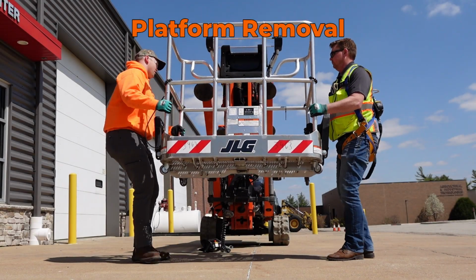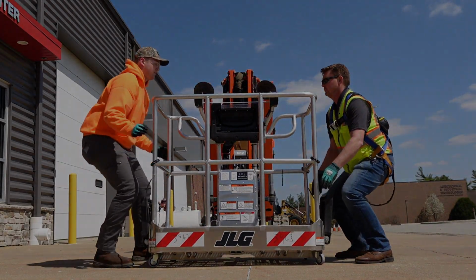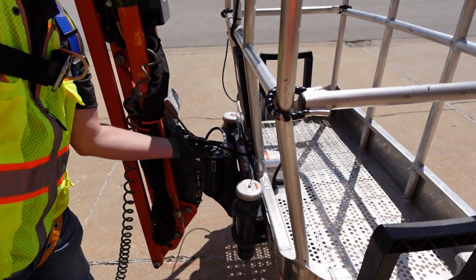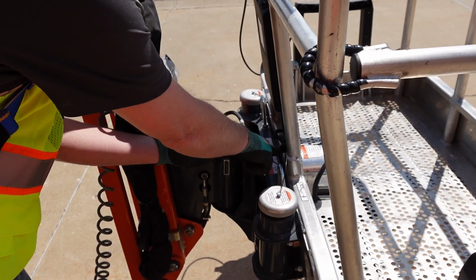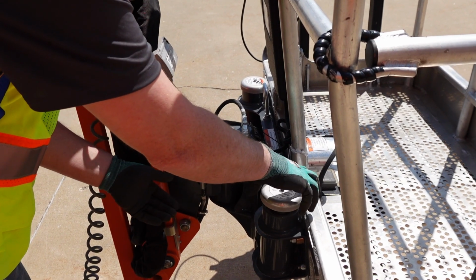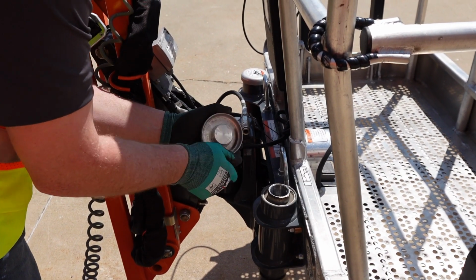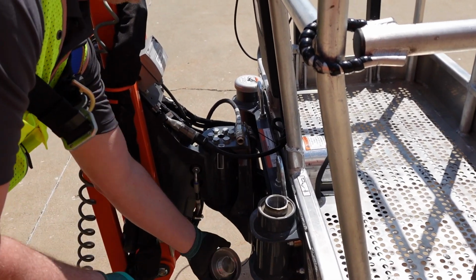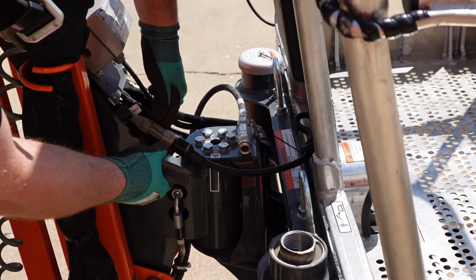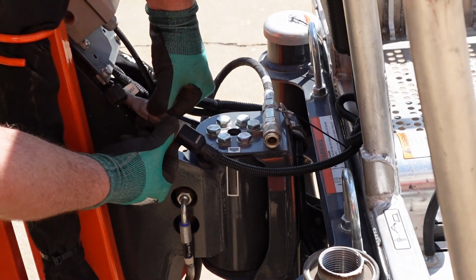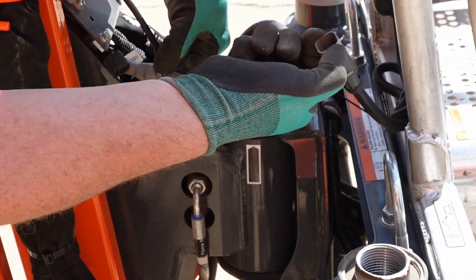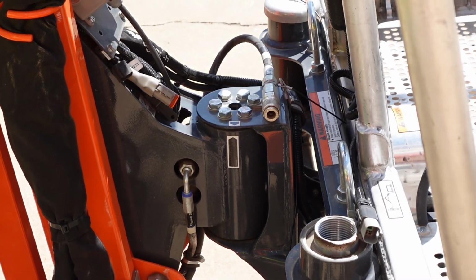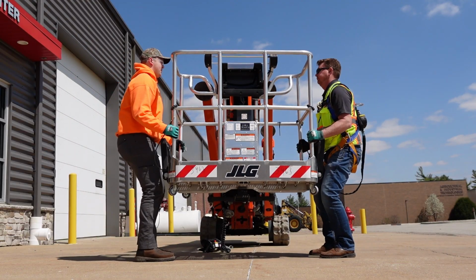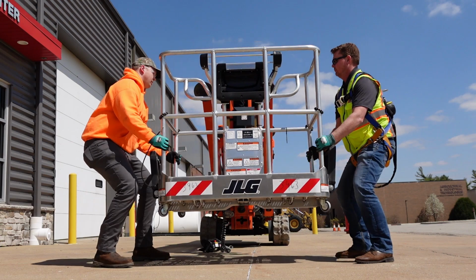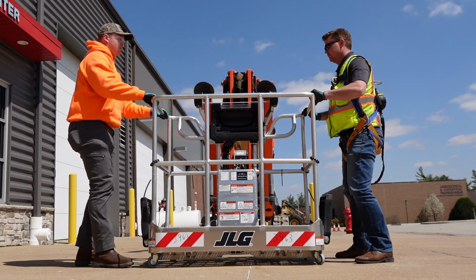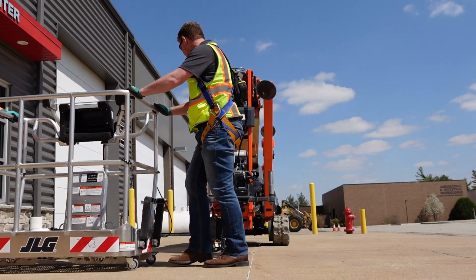The platform of the X660 can be removed for travel through narrow openings. A single wiring harness is connected to the platform. The platform is secured to the machine by 2 large, threaded caps. To remove the platform, unscrew the securement caps on each side of the platform. Next, unplug the wiring harness and place it out of the way. Lift the platform off the machine. This is a 2-person operation. Once on the ground, the platform has casters and can be rolled to the work area and put back on.